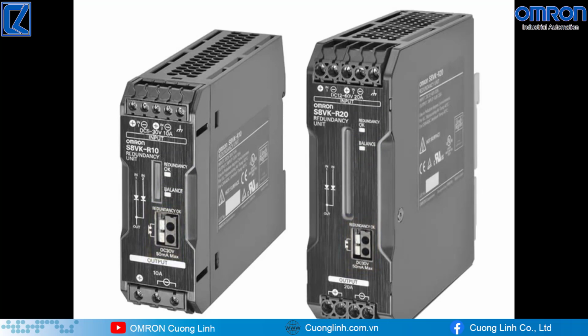The redundancy operating LED will turn on when the input voltage difference is less than 2.4 volts. The LED will turn off if the power supply fails or a connection error causes one of the power supplies not to provide voltage. The voltage balance LED indicates when the voltage difference is 50 millivolts or less. By adjusting the input voltage until the LED is on, the output current of each power supply will be balanced. By balancing the load, the operating life of each power supply should be more than twice when compared to using only one power supply.